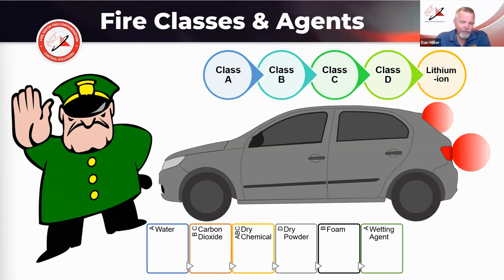Dry powder extinguishers are specifically for Class D, or metals fires. They try to encrust the metals fire and starve it of oxygen until it has time to cool down. Foam as an extinguishing agent is mostly a mechanical feature of fire protection, creating a blanket of bubbles on top of a liquid fuel that is static and not moving. It has to be static for that foam blanket to stay intact—if the fuel is moving or spraying, you have to use a dual agent or a different agent, which we'll discuss in a moment.